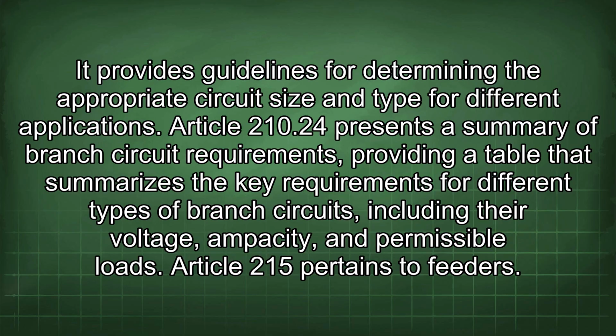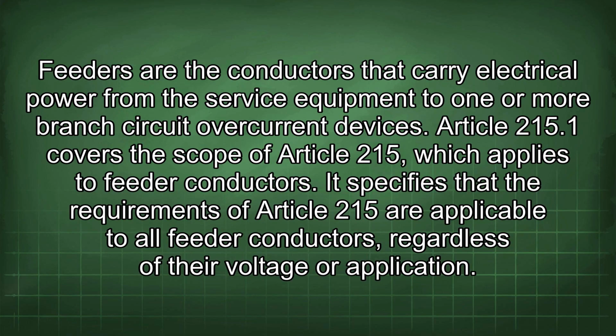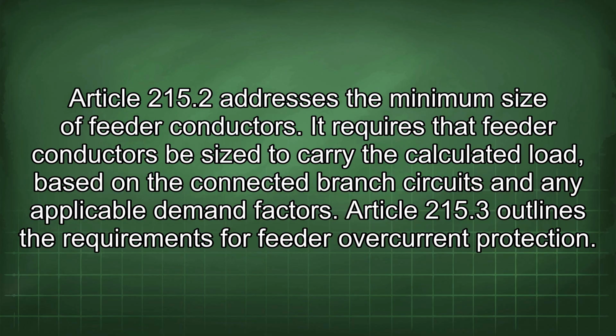Article 215 pertains to feeders. Feeders are the conductors that carry electrical power from the service equipment to one or more branch circuit overcurrent devices. Article 215.1 covers the scope of Article 215, which applies to feeder conductors. It specifies that the requirements of Article 215 are applicable to all feeder conductors, regardless of their voltage or application. Article 215.2 addresses the minimum size of feeder conductors. It requires that feeder conductors be sized to carry the calculated load, based on the connected branch circuits and any applicable demand factors.